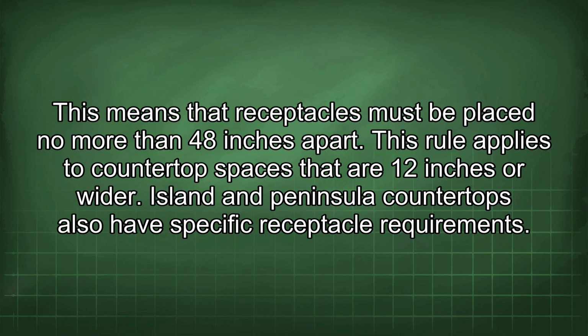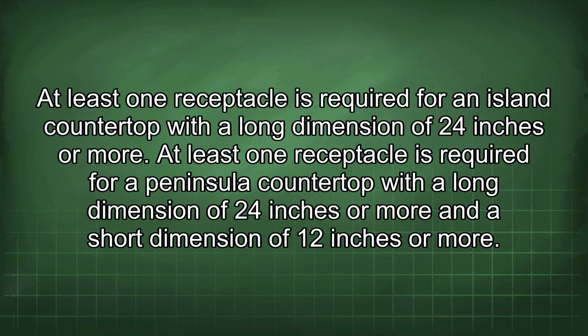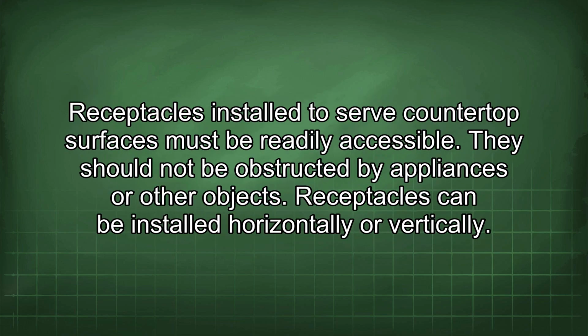Island and peninsula countertops also have specific receptacle requirements. At least one receptacle is required for an island countertop with a long dimension of 24 inches or more. At least one receptacle is required for a peninsula countertop with a long dimension of 24 inches or more and a short dimension of 12 inches or more. Receptacles installed to serve countertop surfaces must be readily accessible. They should not be obstructed by appliances or other objects.